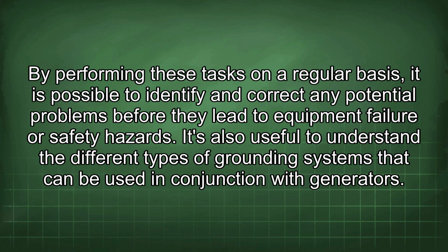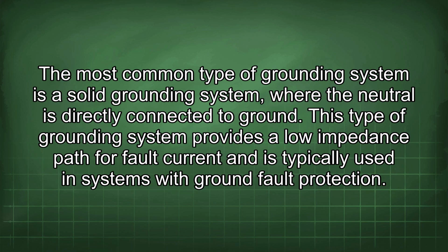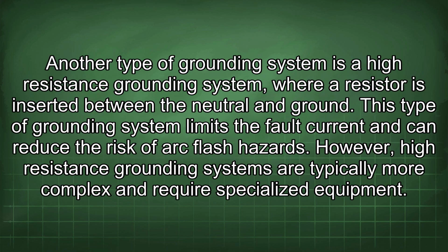It's also useful to understand the different types of grounding systems that can be used in conjunction with generators. The most common type of grounding system is a solid grounding system, where the neutral is directly connected to ground. This type of grounding system provides a low impedance path for fault current and is typically used in systems with ground fault protection. Another type of grounding system is a high resistance grounding system, where a resistor is inserted between the neutral and ground. This type of grounding system limits the fault current and can reduce the risk of arc flash hazards. However, high resistance grounding systems are typically more complex and require specialized equipment.